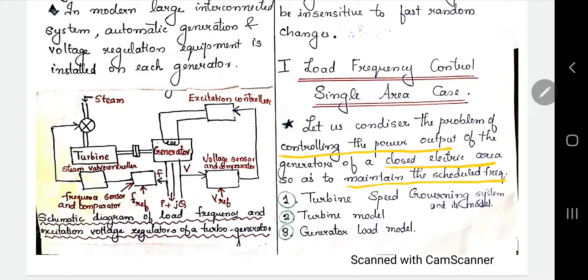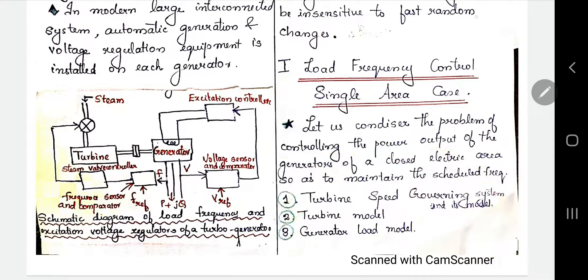We are considering a single control area, where the power output of the generators is being controlled so as to maintain the scheduled frequency. This will be understood only by analyzing a complete steady state model. The steady state analysis can be done only after getting the models of three different parts: the turbine speed governing system, the turbine model, and the generator load model. By combining these three models, we can perform a steady state analysis to study load frequency control.